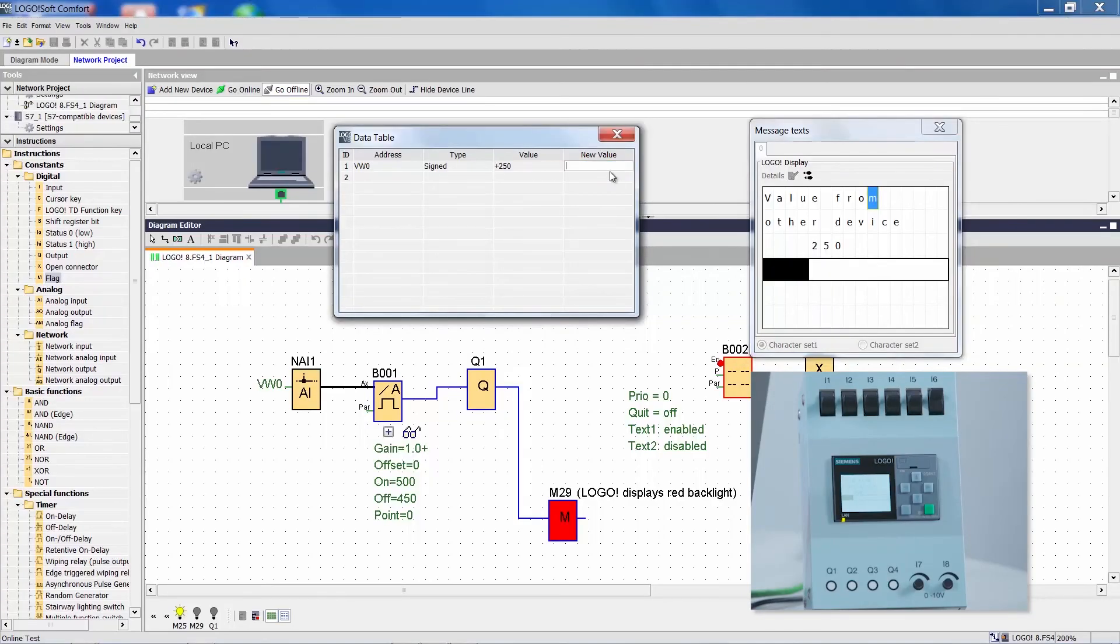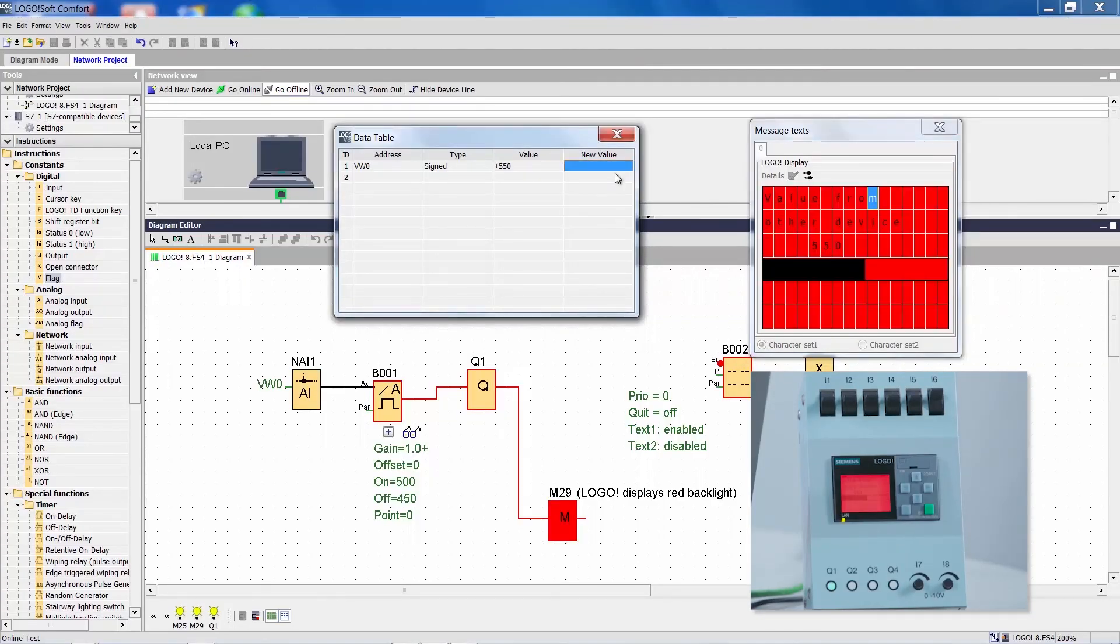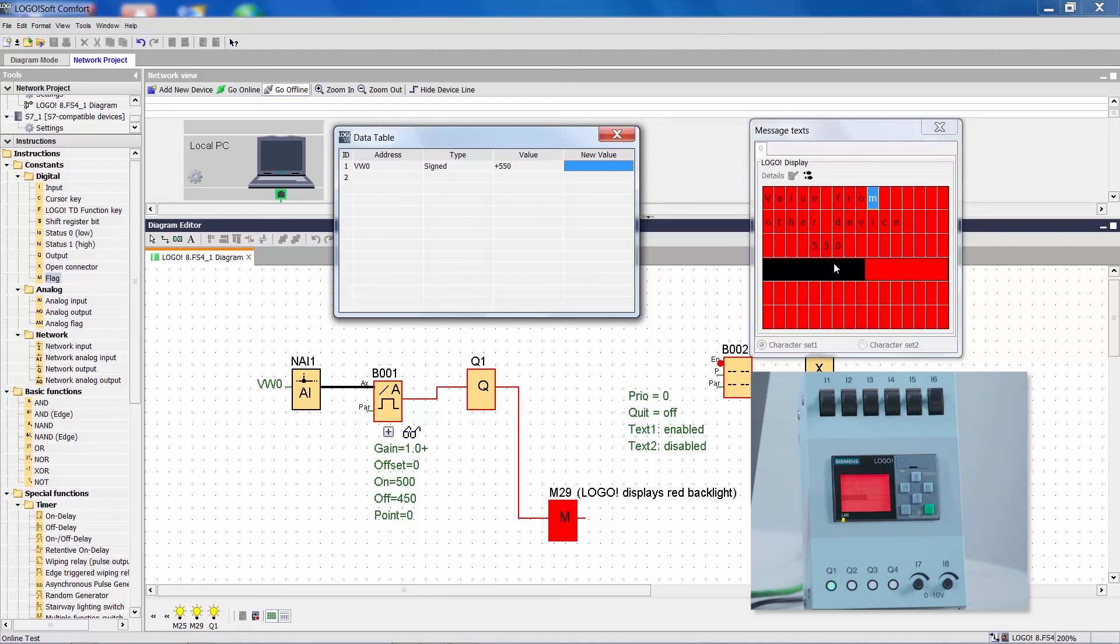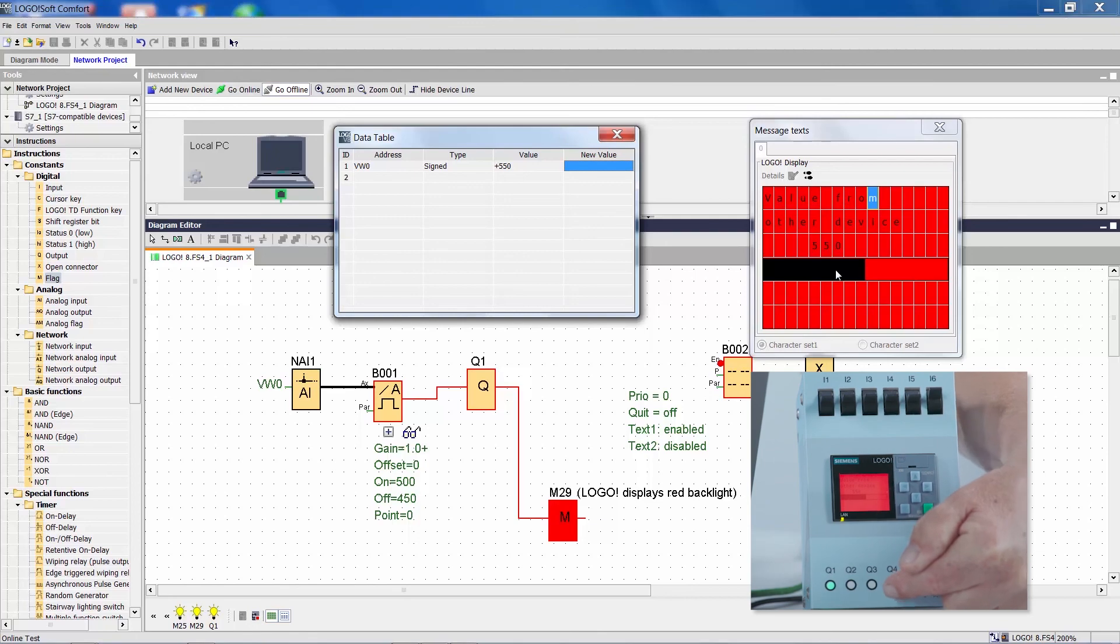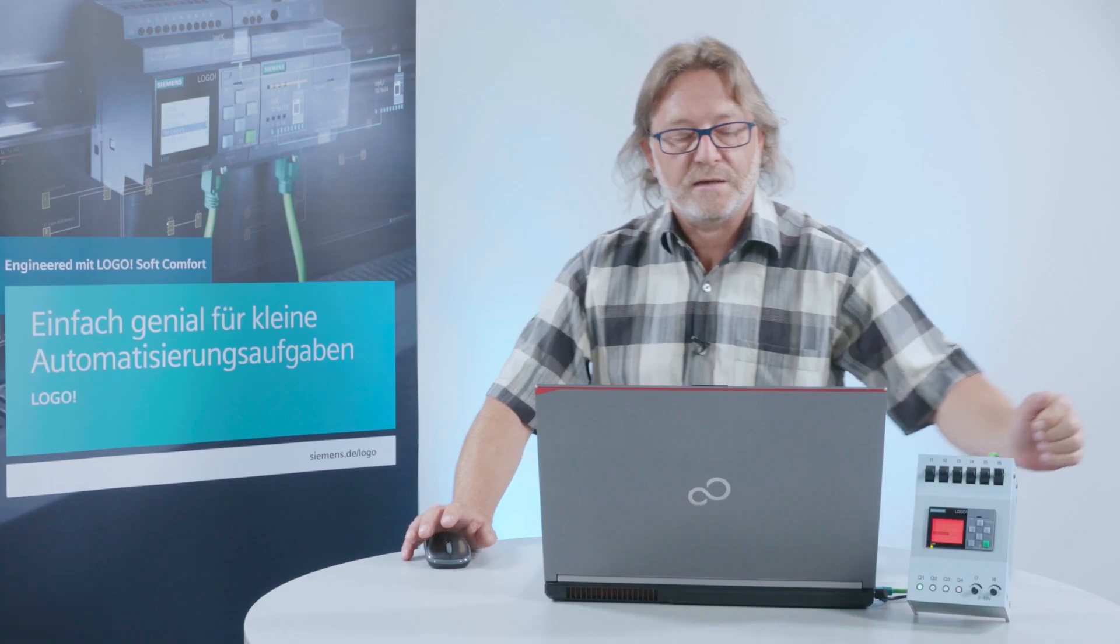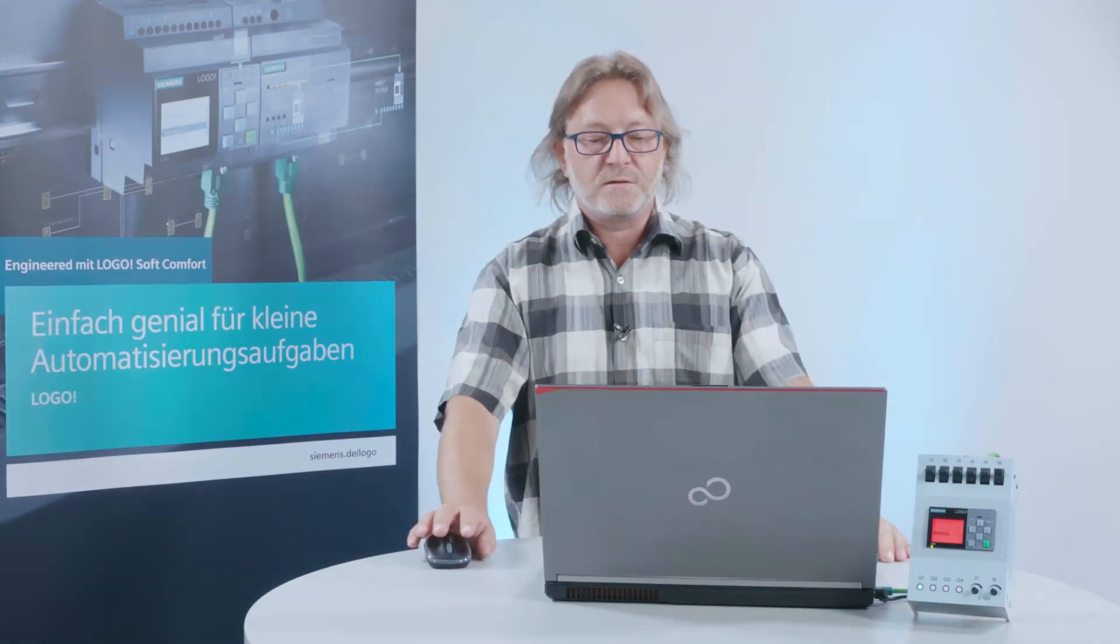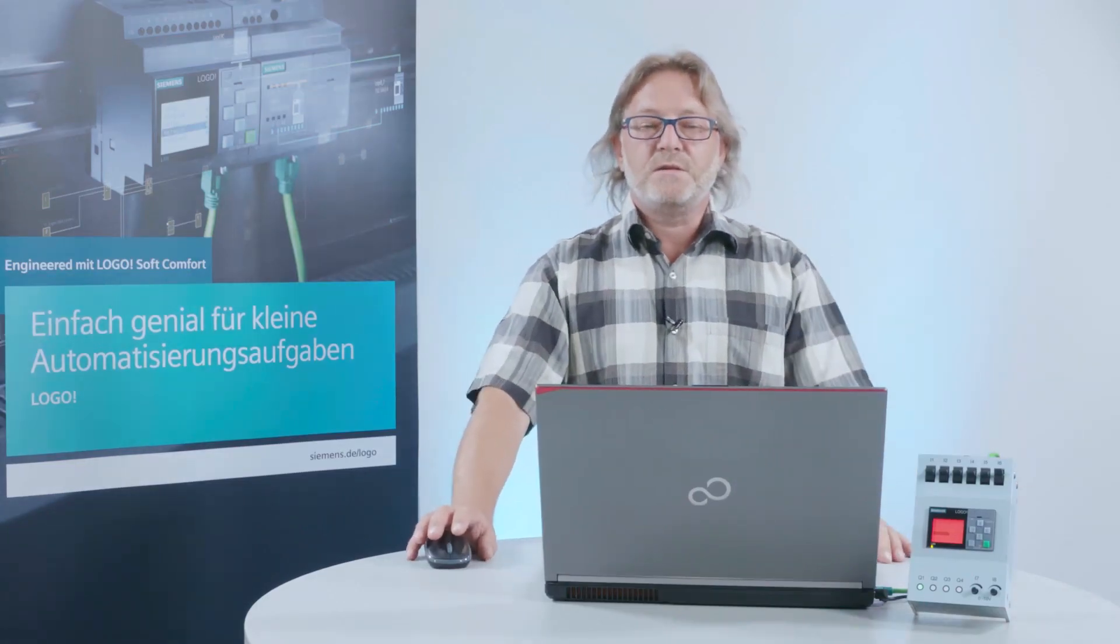If the value should now rise above the specified threshold value of 500, we can see here in the visualization that the display color changes to red and the bar graph and the value are updated. We see the same right here in the device and output 1 is also activated.